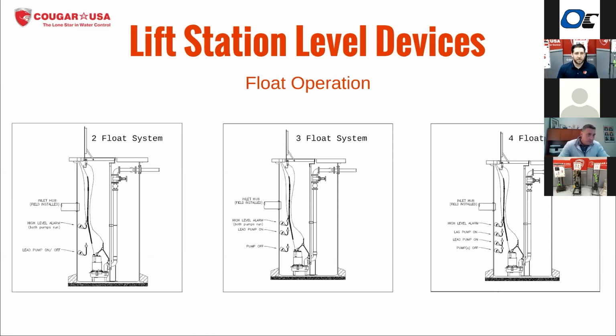The third float switch at the top is going to give you the high level alarm and turn both pumps on. So again, as soon as your lag pump runs, you're going to get that high level alarm. In a sanitary application, that's what we would want to see. We want to get that high level alarm when the lag pump runs.